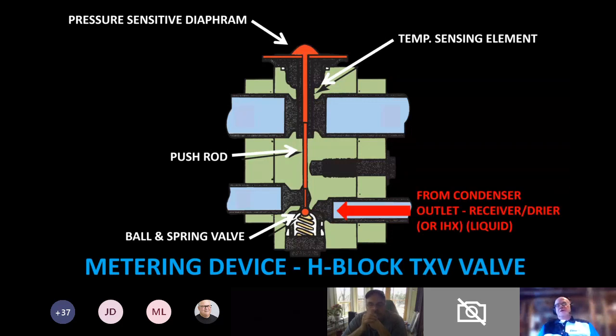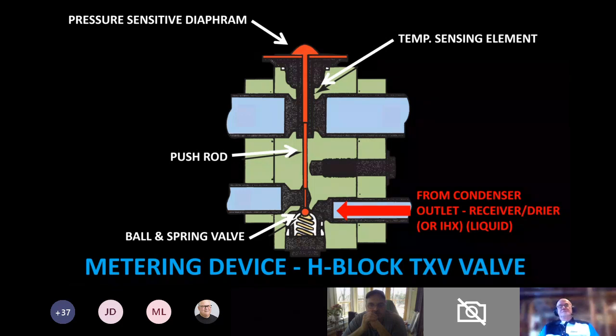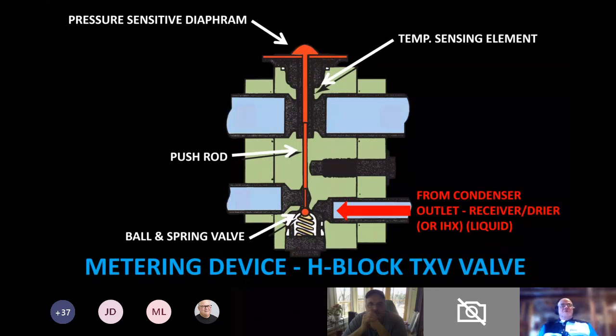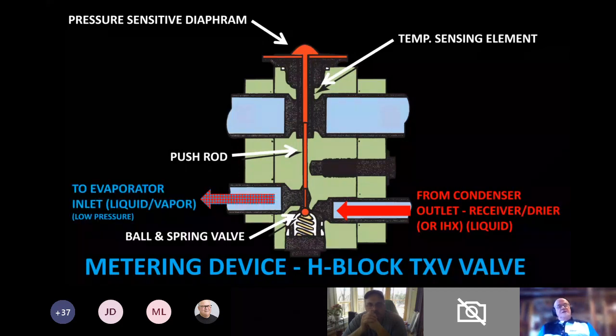So from the condenser, we have liquid flowing into the H block, usually at the bottom. Now it comes from the receiver dryer, or if the car has an IHX, it would come from there. It is a liquid refrigerant under high pressure and high temperature. After the valve modulates that flow, it changes state to a low pressure liquid with a little bit of vapor in it, maybe depending on conditions, and it enters the evaporator. So there's your metering device. That's where the orifice tube would be if it was an orifice tube system.